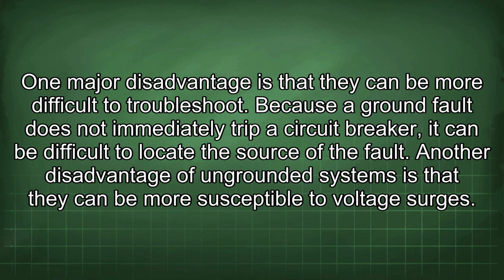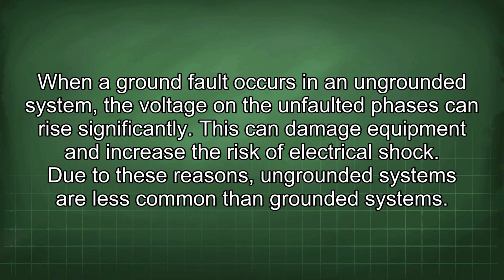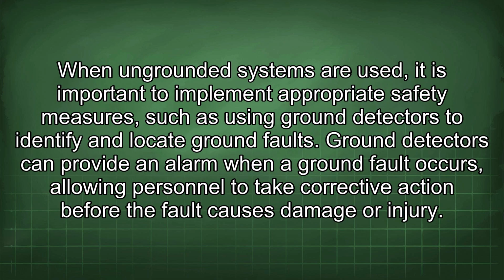Another disadvantage of ungrounded systems is that they can be more susceptible to voltage surges. When a ground fault occurs in an ungrounded system, the voltage on the unfaulted phases can rise significantly. This can damage equipment and increase the risk of electrical shock. Due to these reasons, ungrounded systems are less common than grounded systems. When ungrounded systems are used, it is important to implement appropriate safety measures, such as using ground detectors to identify and locate ground faults. Ground detectors can provide an alarm when a ground fault occurs, allowing personnel to take corrective action before the fault causes damage or injury.